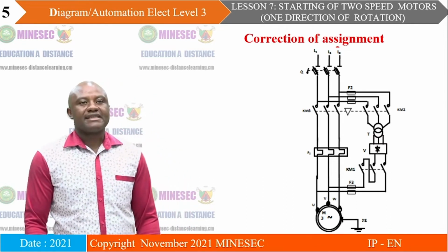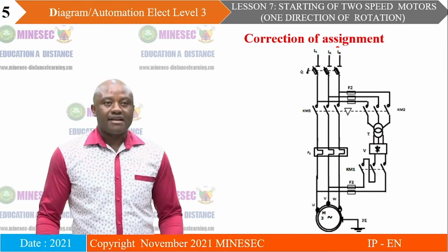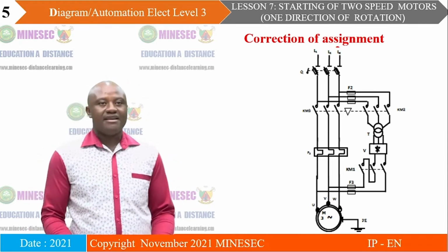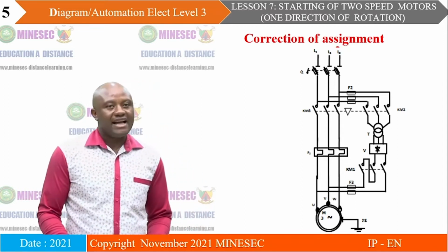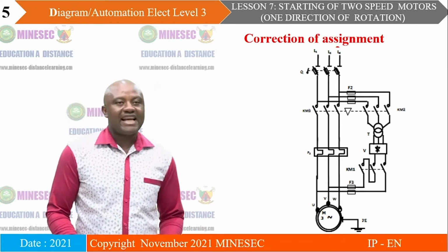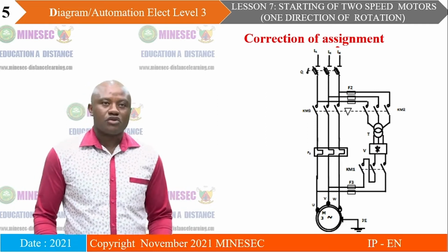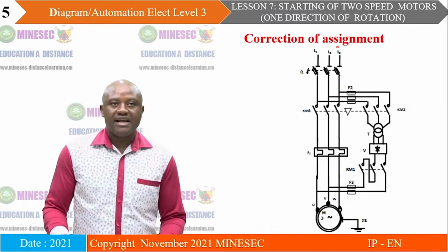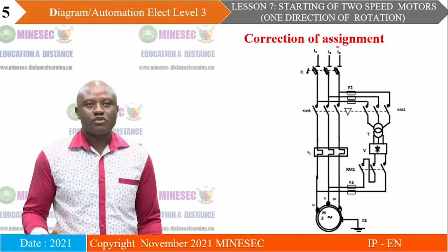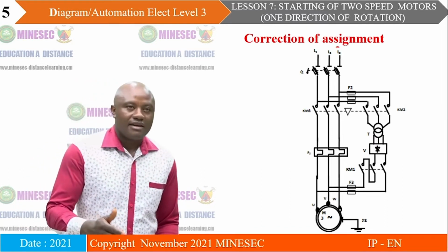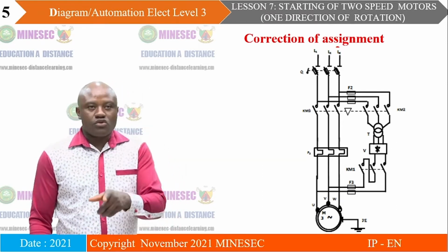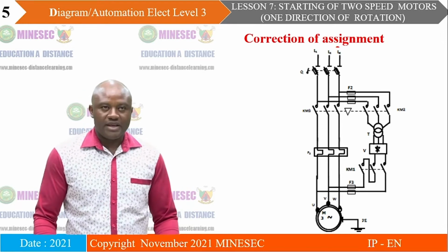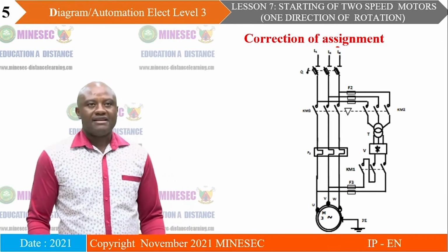When you start the motor with contactor KM1, the motor is running normally, and if you desire to stop the motor, you press stop, and the contactor KM1 stops functioning. Automatically KM2 will start, and DC current will be injected into the motor circuit. In that case, the motor will be completely stopped and the rotor is standing.